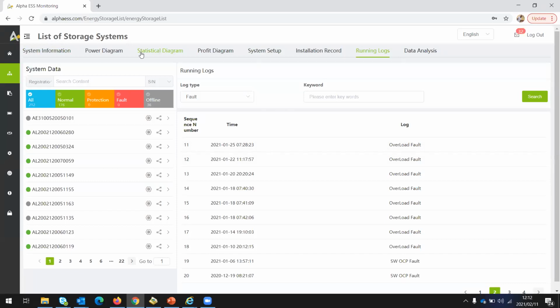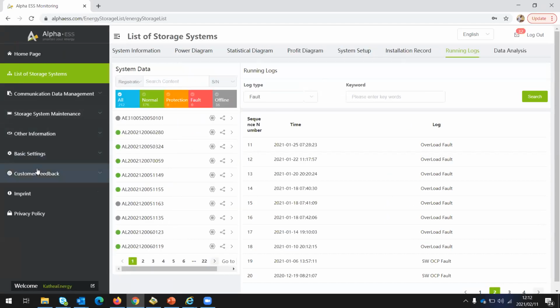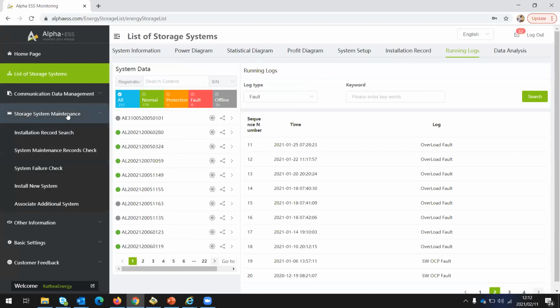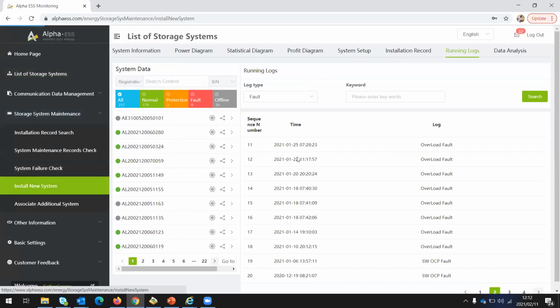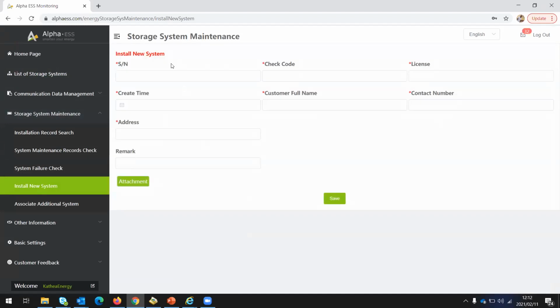So to register the system, sorry, I forgot. Once you have installed the system, you log in to your account, then you go to system storage maintenance, and then you select install new system. It will open up another page. Here you need the serial number of the system that you installed. Under the serial number there is a code, either written verification code or check code. That's the one that you input here on check code.